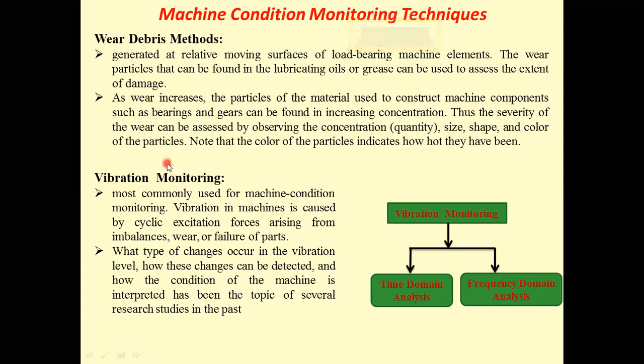One note is that the color of the wear particle indicates how hot they have been, or what the temperature of that wear particle is. So this is another method by which we can monitor the condition of a machine.